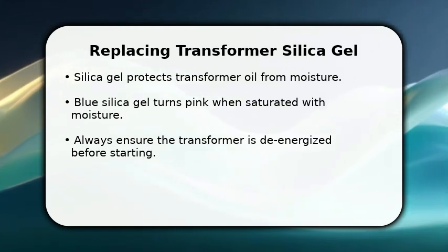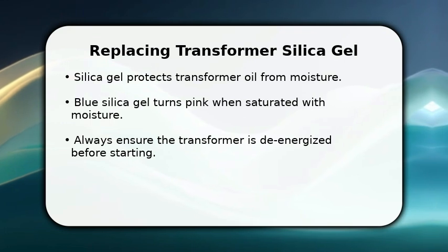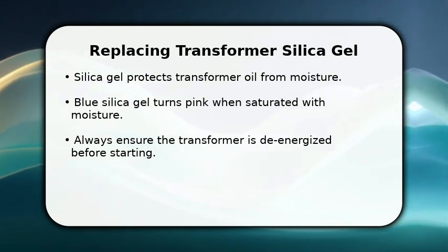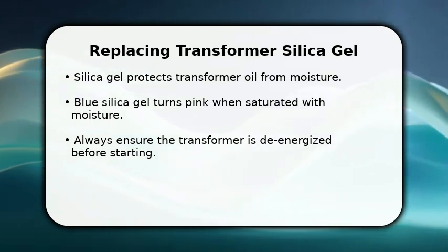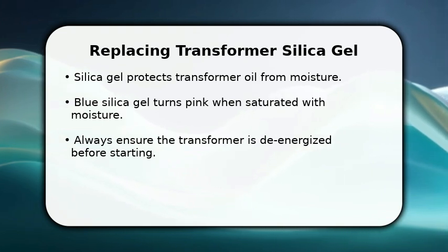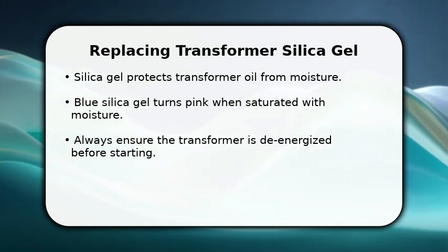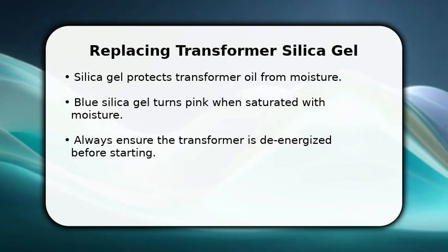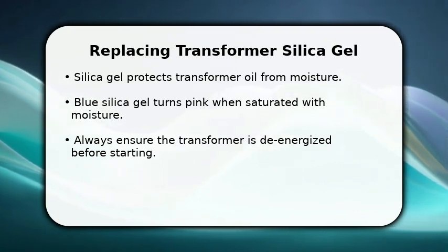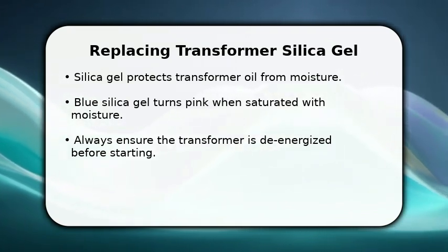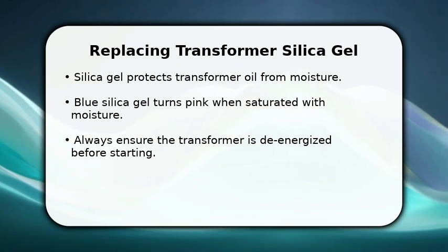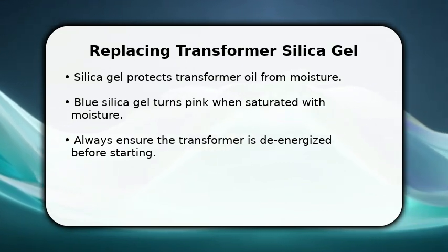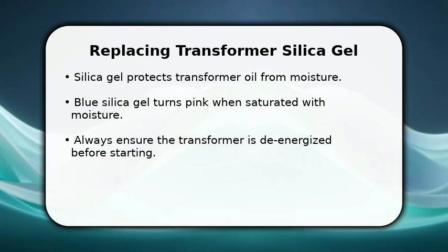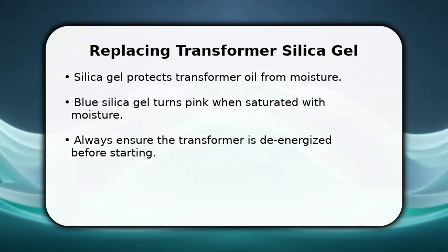First, confirm the transformer is completely de-energized and isolated from all power sources. Safety is paramount, so double-check all lockout/tagout procedures. You'll need new, active silica gel, typically blue, and appropriate personal protective equipment. This process ensures the transformer's longevity and efficient operation by preventing moisture contamination of the insulating oil.